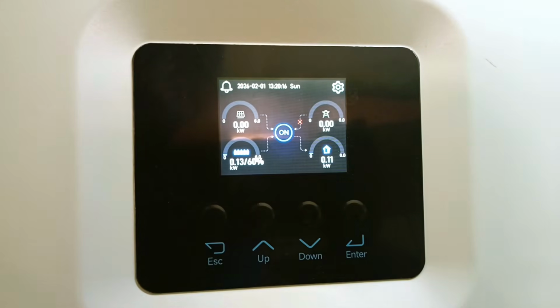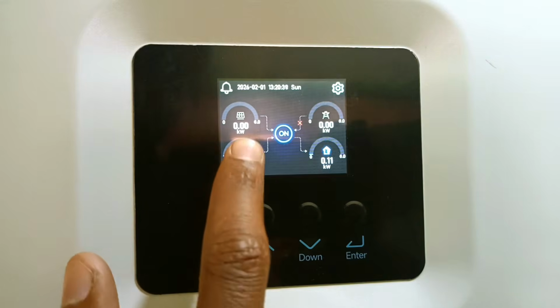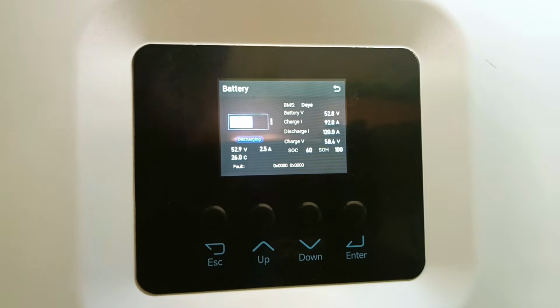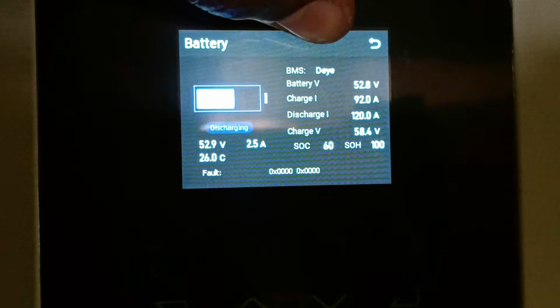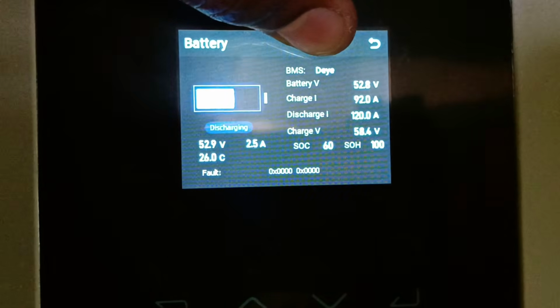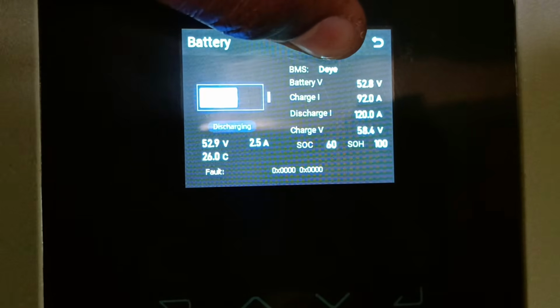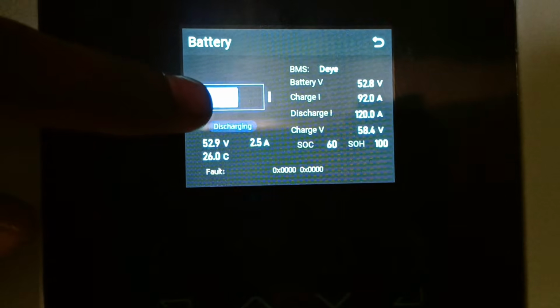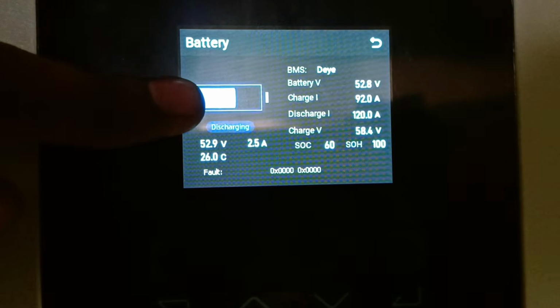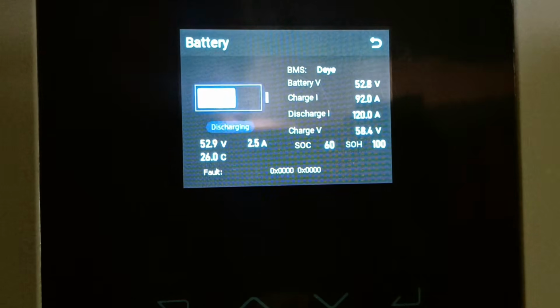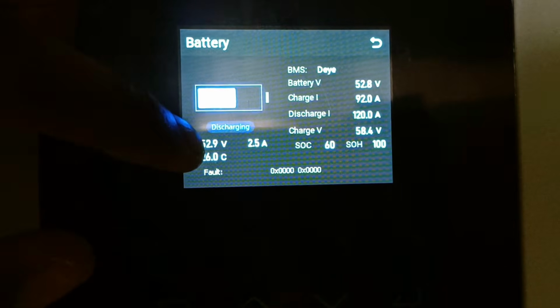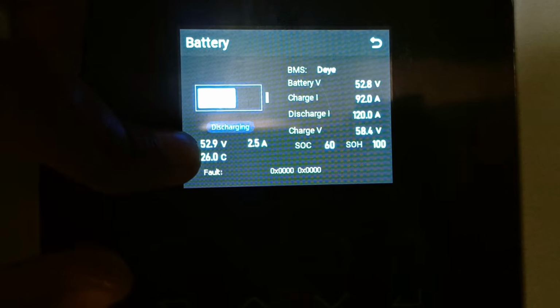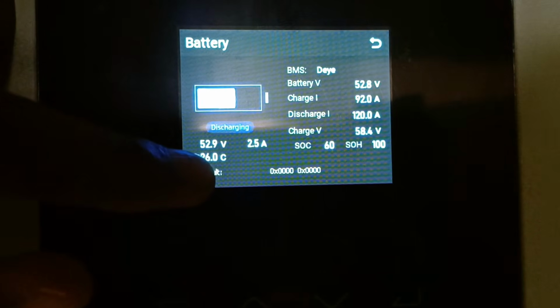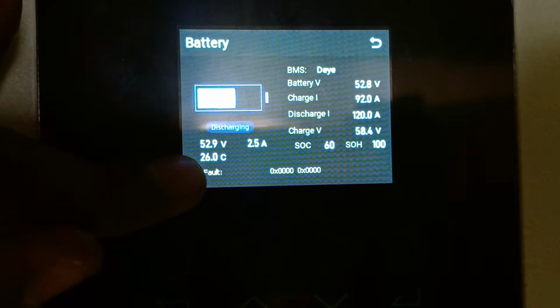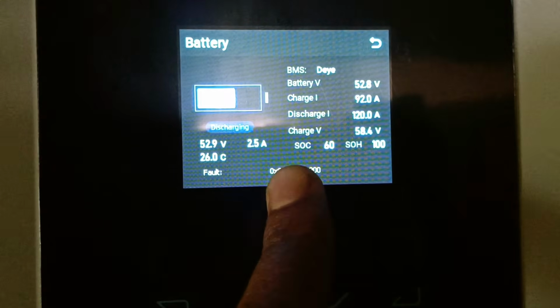So those are all the settings of the Deye Sun 6K inverter. Let's now check the battery information since the inverter and the battery are communicating well. The BMS says it's a Deye inverter. I know if I had a different brand of battery, it would communicate and say its name here. The battery is at 60% state. I know you can't see that because of my camera, but it's 60%. It's discharging. The battery voltage is 52.9 volts at 2.5 amperes, and the battery temperature is 26 degrees Celsius. Currently, the battery does not have any faults.